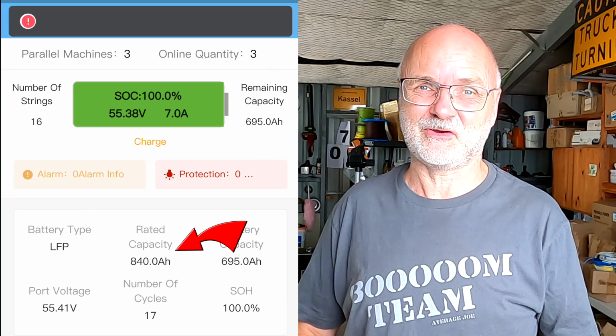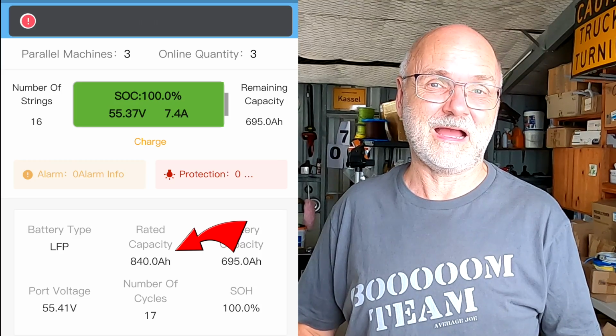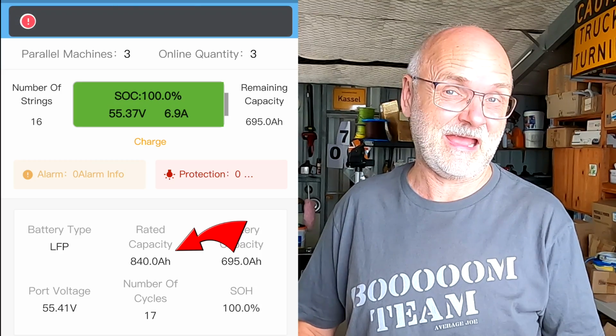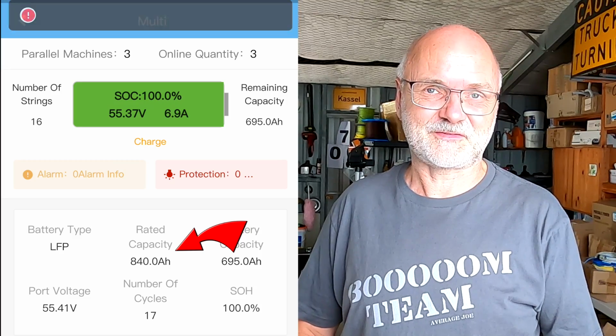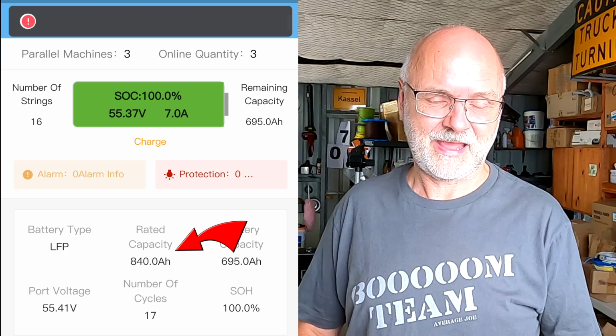Unfortunately, the Seplos master only assumes that all the other slaves are the same capacity as itself, so it takes 280 ampere hours times 3, which is 840.